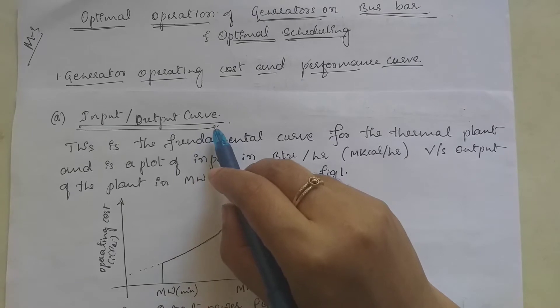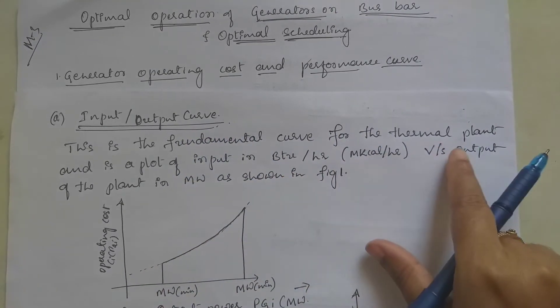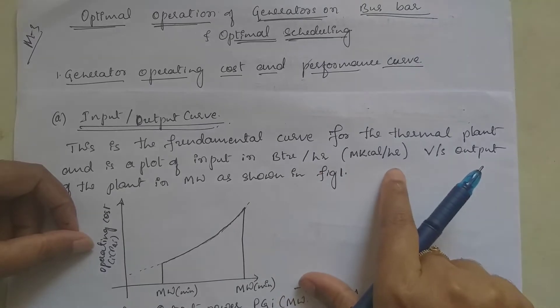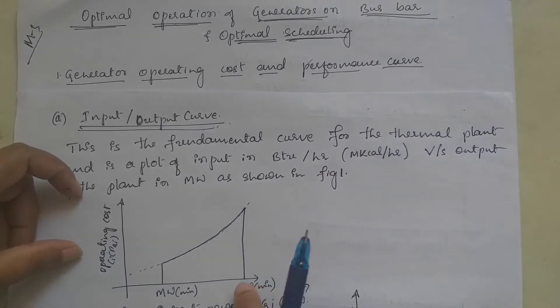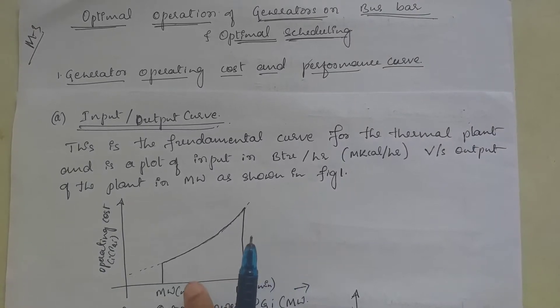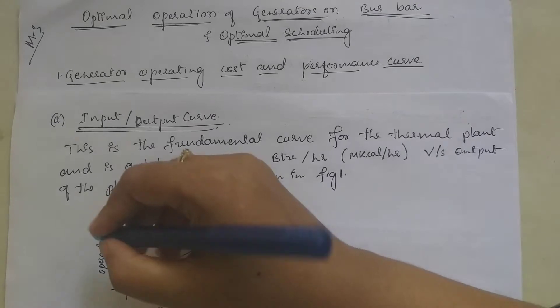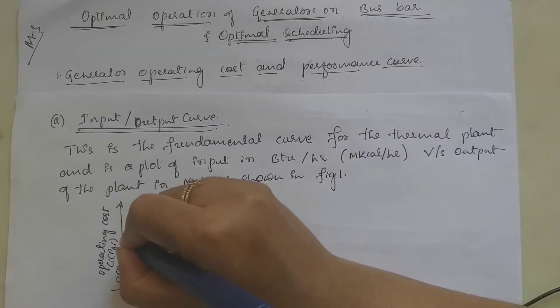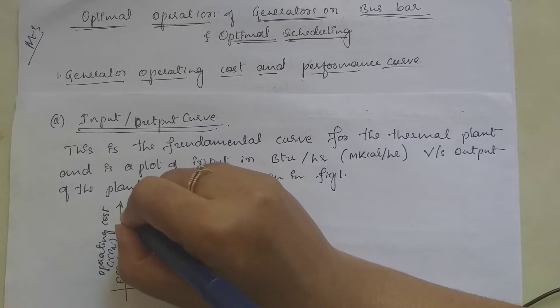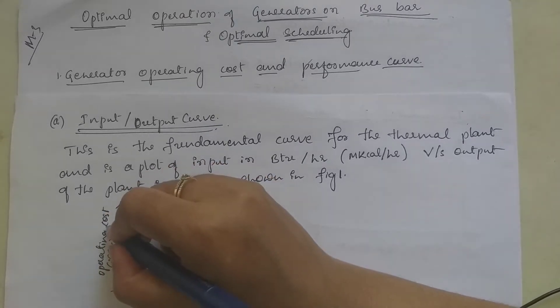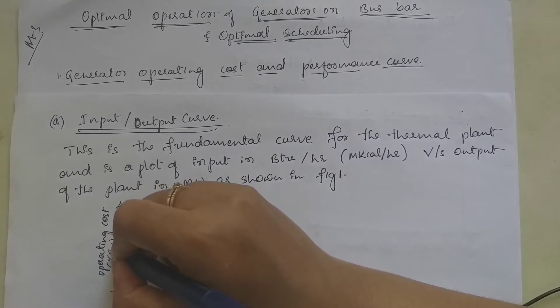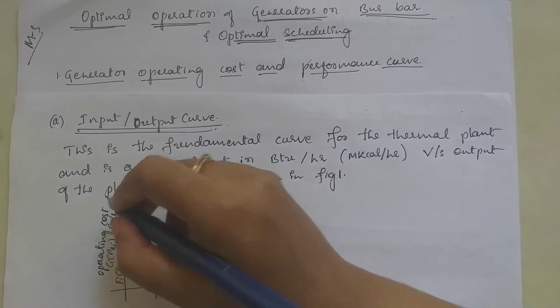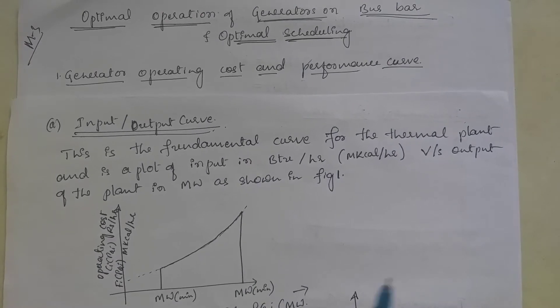The first curve is the input-output curve. This is the fundamental curve for the thermal power plant and it is the plot of input in British thermal units per hour or m kilocalorie per hour versus output of the plant. The input-output curve of generating units specifies the input energy rate represented by Fi(PGi), with units of m kilocalorie per hour, or the operating cost Ci(PGi) in rupees per hour, as a function of generator power output PGi in megawatt.